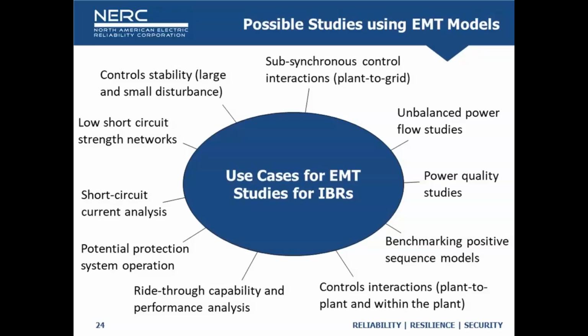I'm not going to go into each one of these, but ride-through capability and performance is a big one, particularly for unbalanced grid conditions. Testing low short circuit strength conditions, control instability type conditions, verifying or developing a short circuit model, even in some cases doing unbalanced power flow, subsynchronous control interaction type studies.